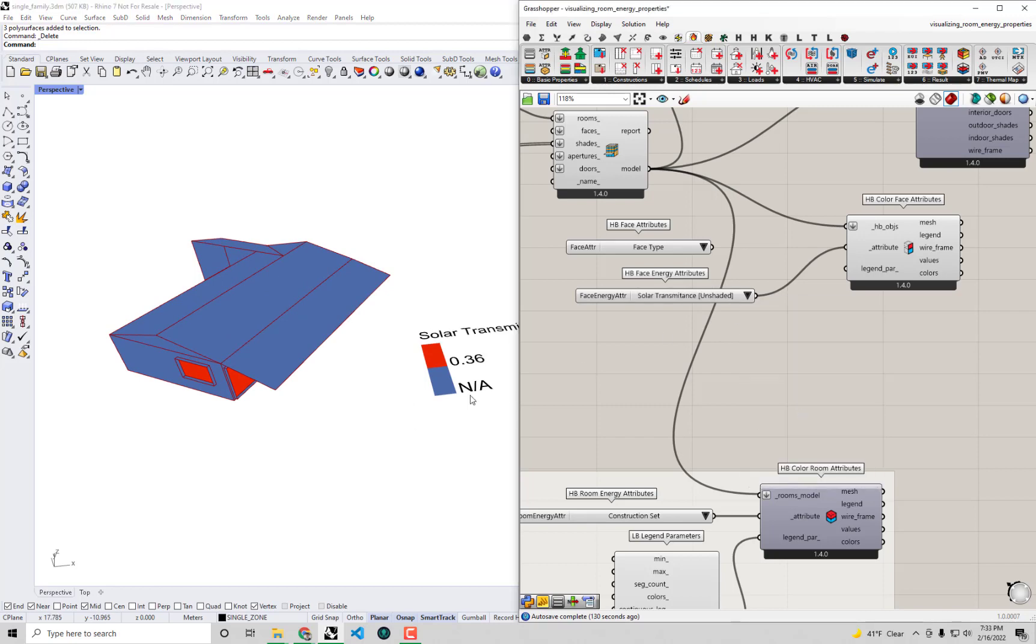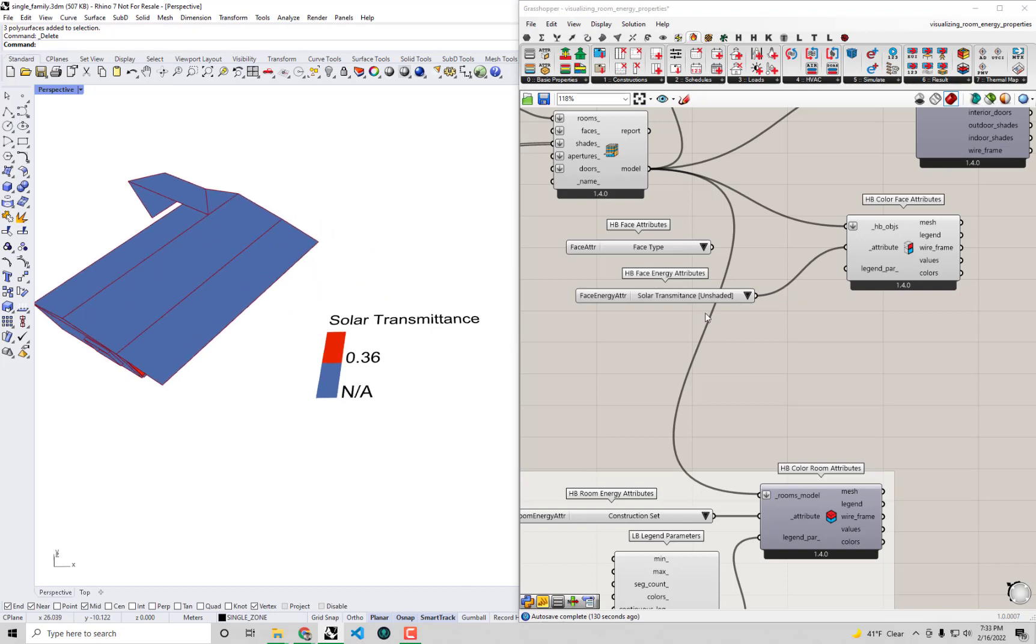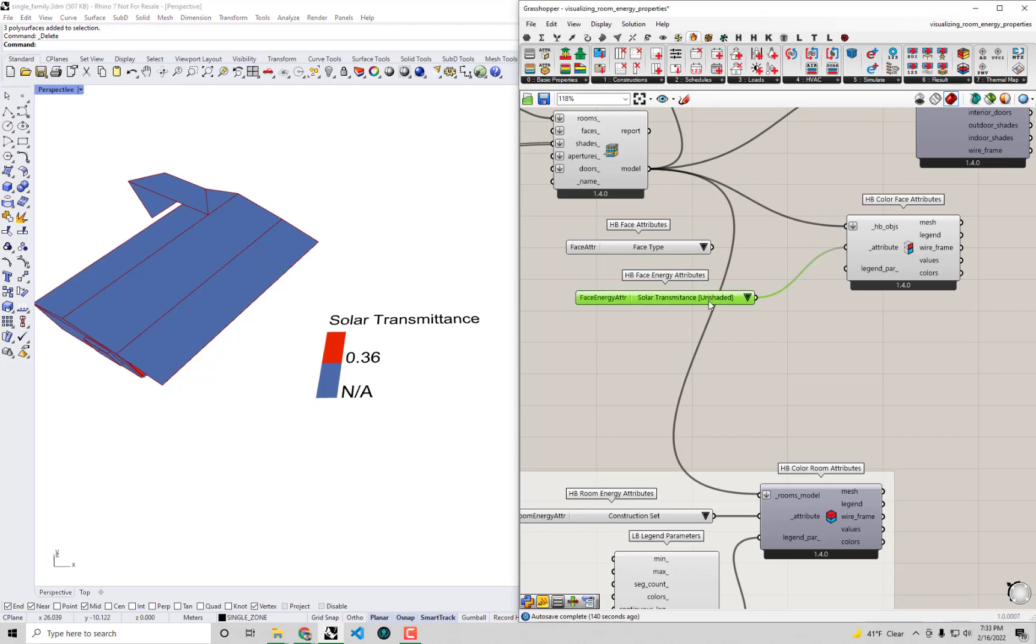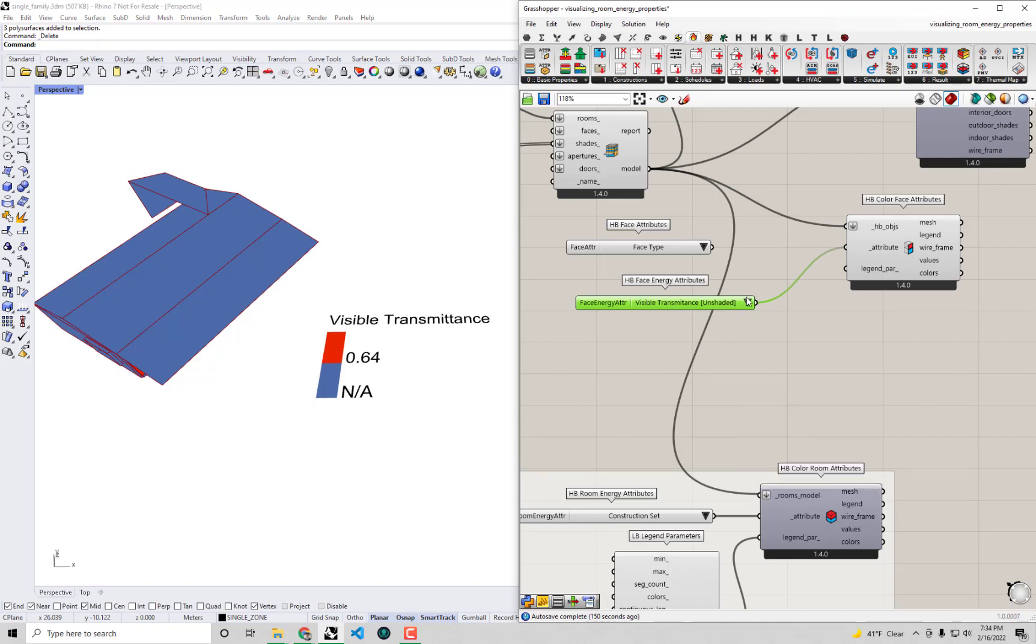Let's see what else can we see. We can see the solar transmittance. Whereas the solar heat gain coefficient includes both the transmitted solar energy as well as the energy from the sun that gets absorbed by the glass and then conducts to the interior, this is looking at just that solar transmitted portion, so just that energy that is directly transmitted.